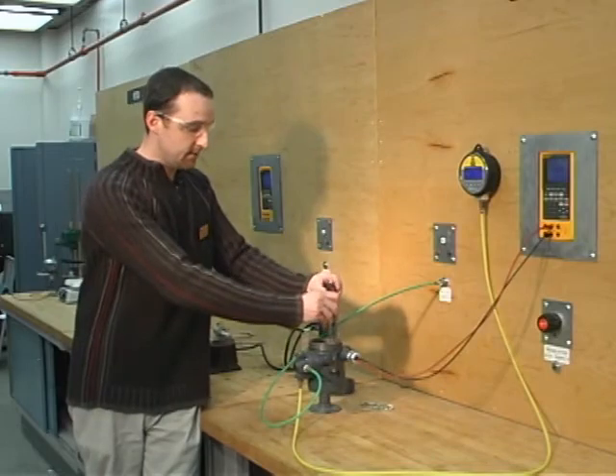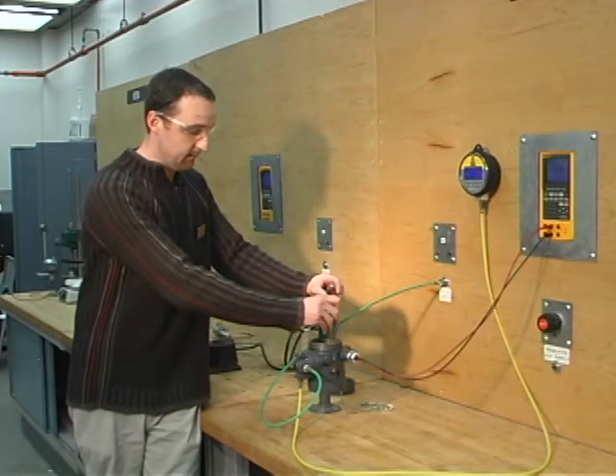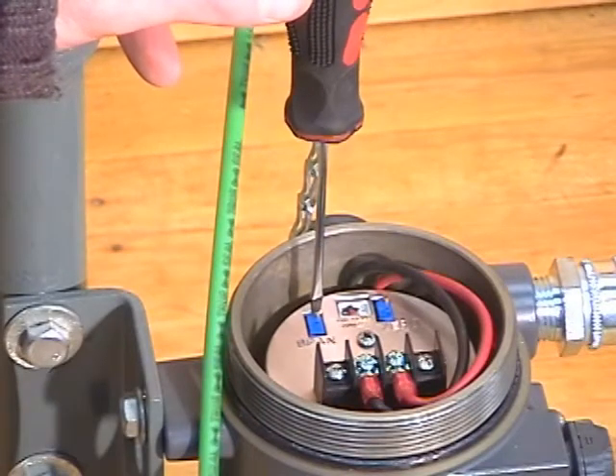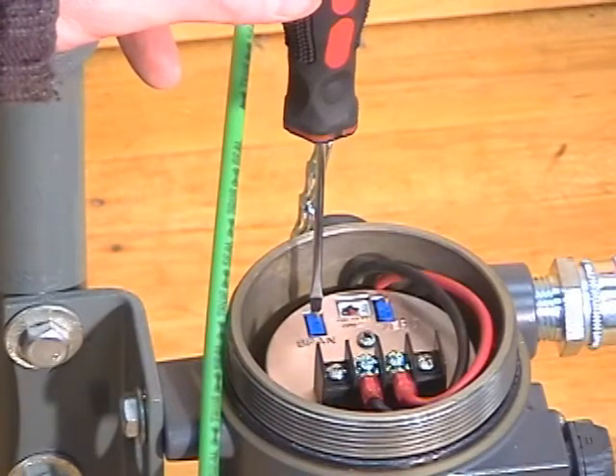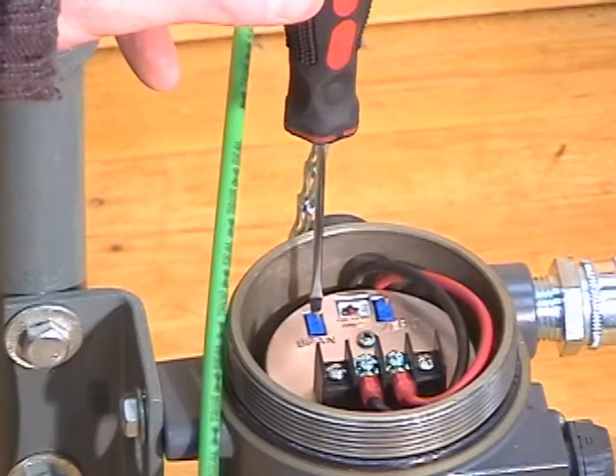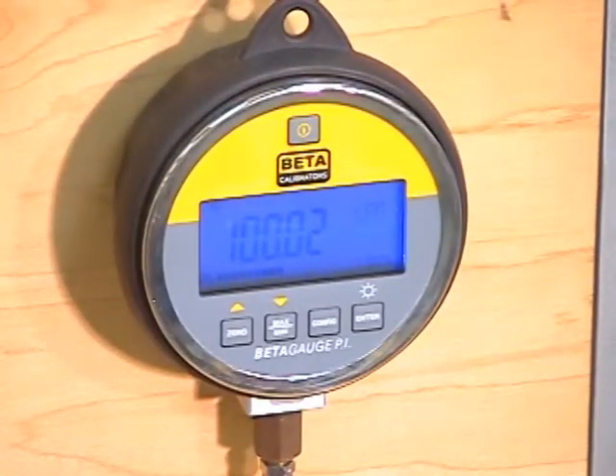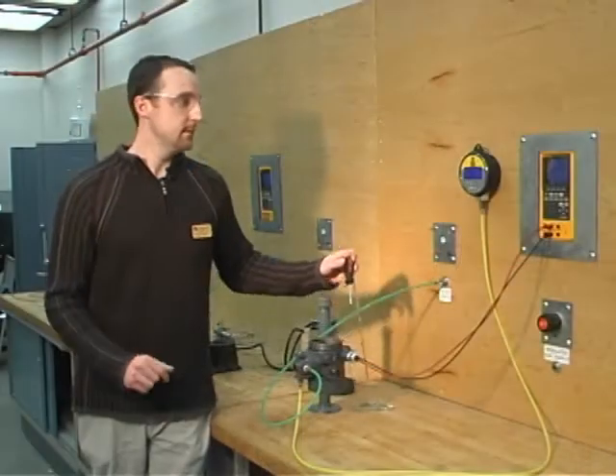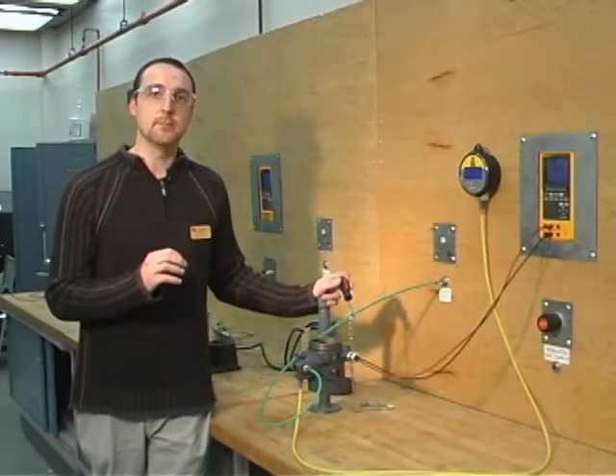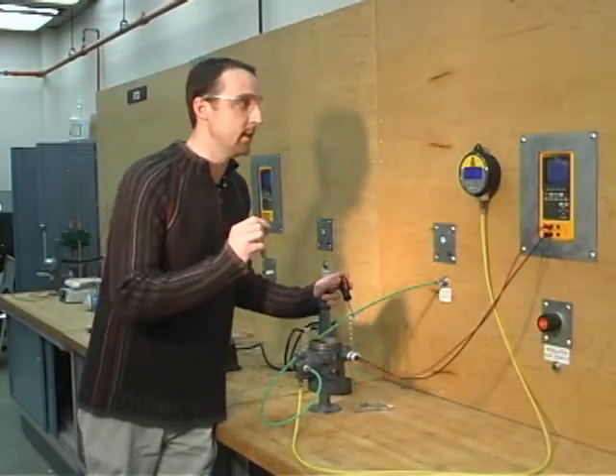So I'm just going to adjust our span here for 100 kilopascals. Usually through a transmitter or transducer calibration, we like to do this step at least twice to verify that the calibration has taken place and is stuck into the transmitter.